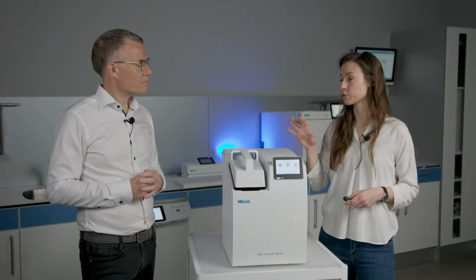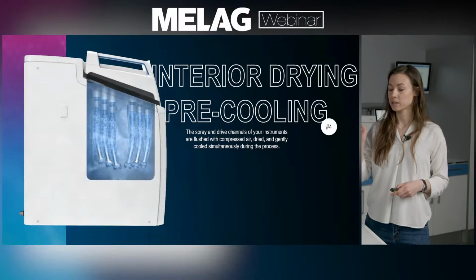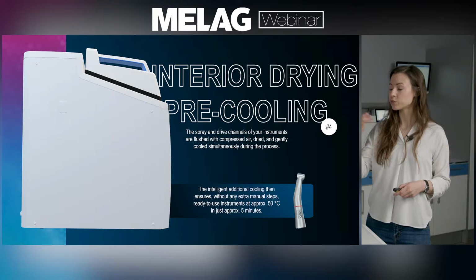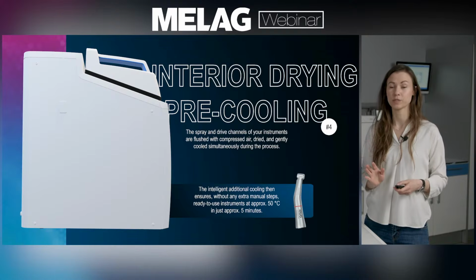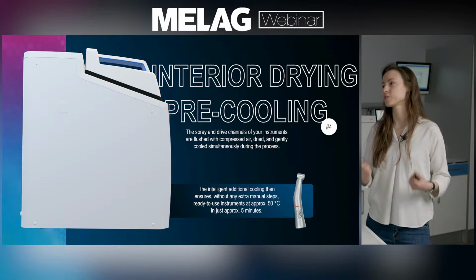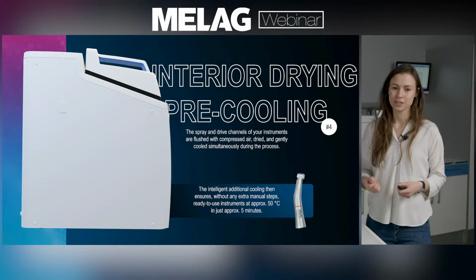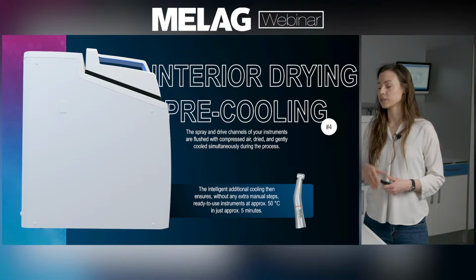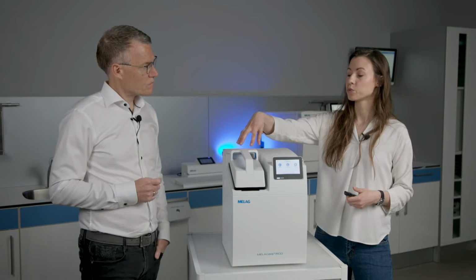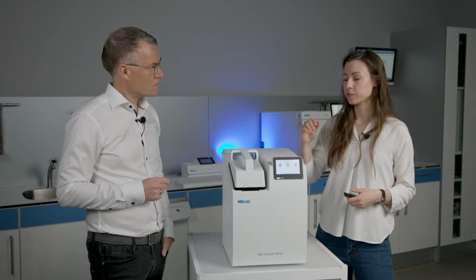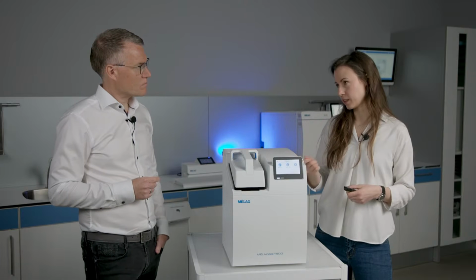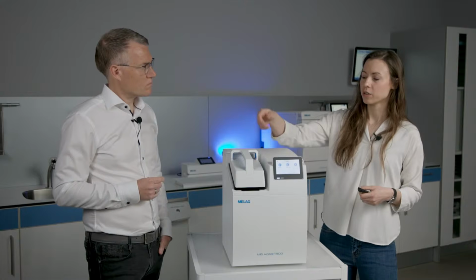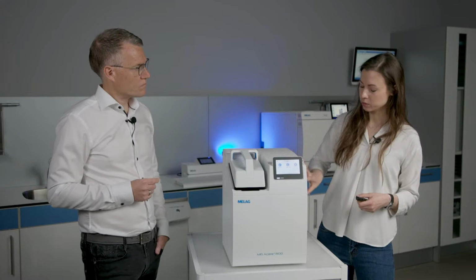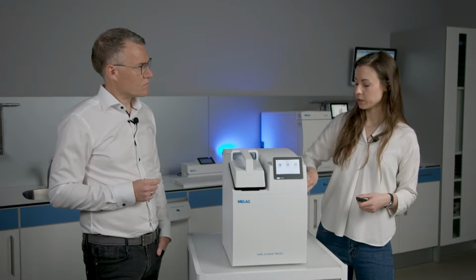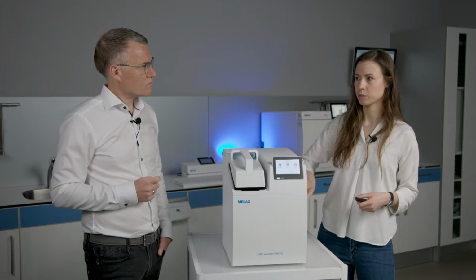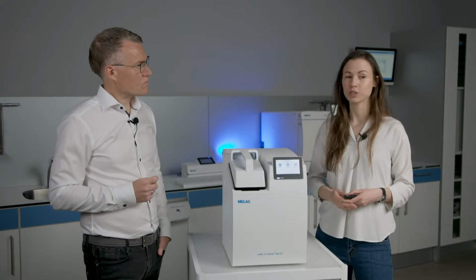We use compressed air to dry the instruments, and then there's an integrated cooling process that takes approximately 5 minutes, so you don't burn your fingers when taking the instruments out and can use them right afterwards. You can let your instruments cool within the chamber, or if you need to start your next cycle quicker, you can take off the lid and use adapters to place it with the instruments to cool down on the side of the device — on the left or right, depending on your setup.